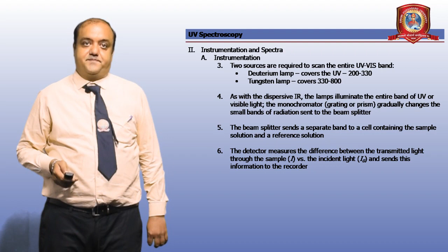The monochromator, grating or prism, gradually changes the smaller band of radiation sent to the beam splitter. The beam splitter sends a separate band to a cell containing the sample solution and a reference solution. The detector measures the difference between the transmitted light through the sample versus the incident light and sends this information to the recorder. As with dispersive IR, time is required to cover the entire UV visible band due to the mechanism of changing wavelength. A recent improvement is the diode array spectrophotometer.